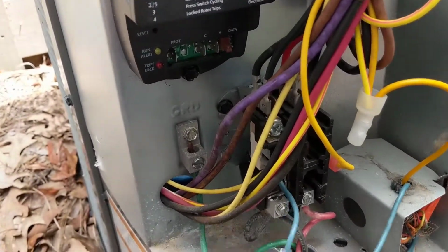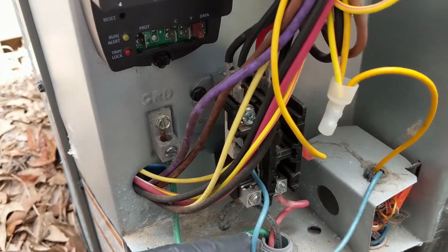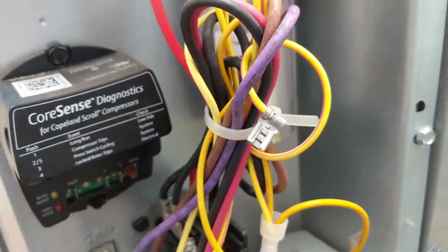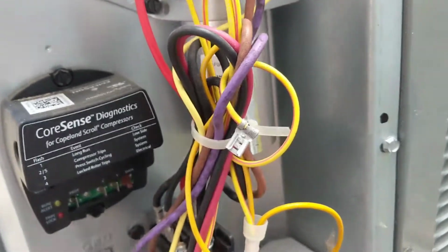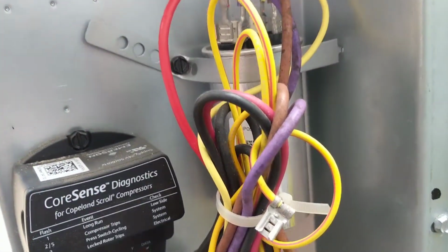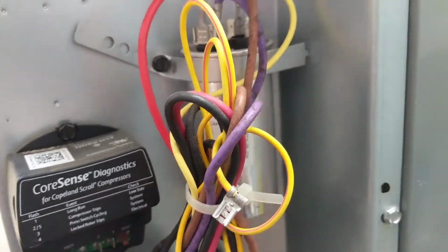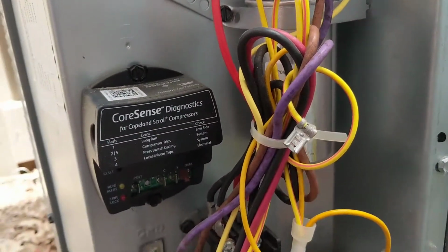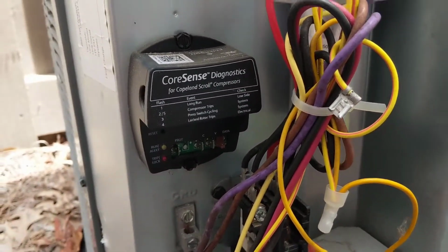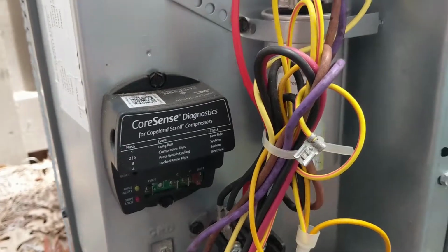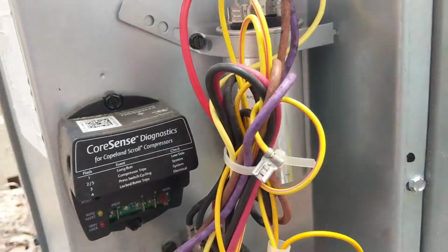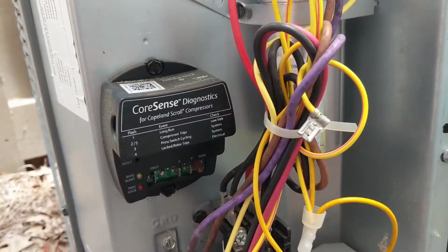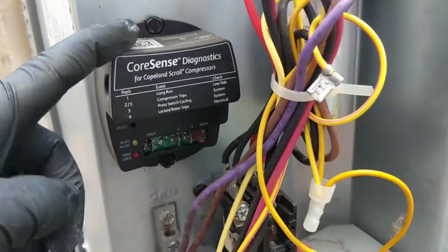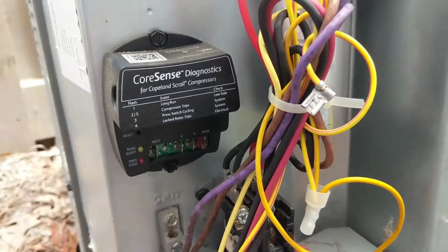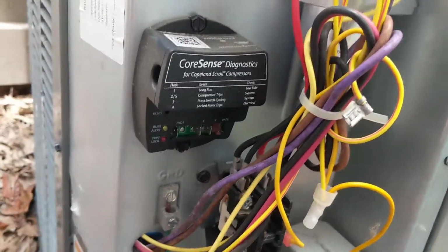So I took my meter across the common here and this terminal here and got 27 volts. So there's definitely still voltage going there with it being tied in. So it just shorted out, touched the cabinet, and blew our little 3-amp fuse. So I'm gonna cut that off and probably wire nut it. That way it doesn't happen again. I don't know who unhooked that, but it is what it is.